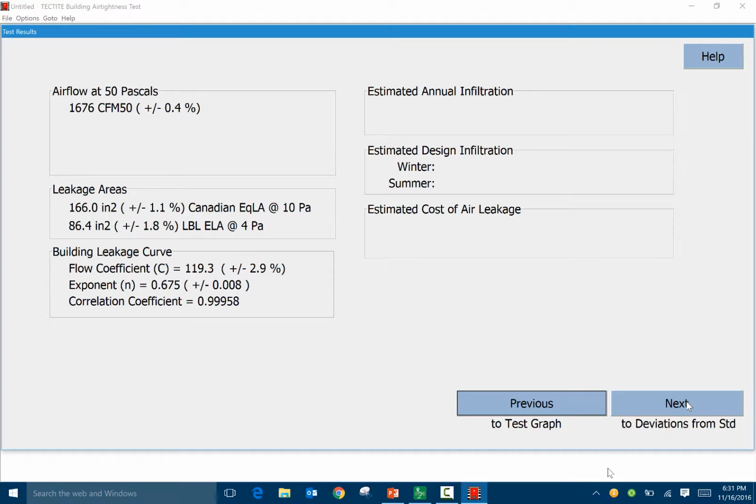It's always a good idea to check our results before our test is over, and we've got a really good correlation here. Anything above 0.99 is a good test. That means those data points are falling into line really well, and our accuracy is good here.